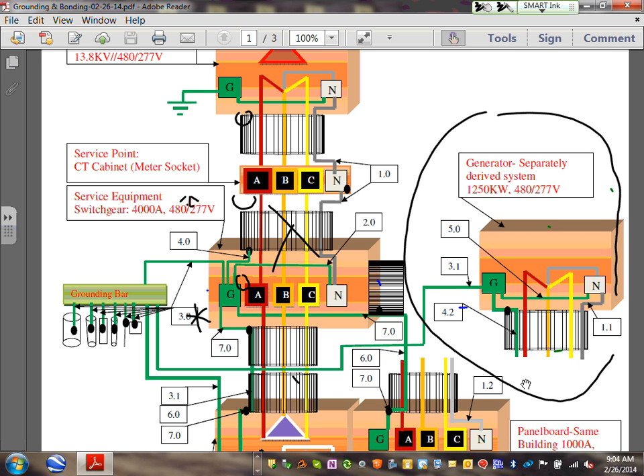For the calculation I'm going to do right now, guys, it doesn't really matter whether it's separately derived or non-separately derived. I'm assuming it's a separately derived system. On my system, I have a 1250 kW generator. The voltage is the same as the one that you guys have. I need to size the following. Number 1, the system bonding jumper, also called the system bonding jumper.